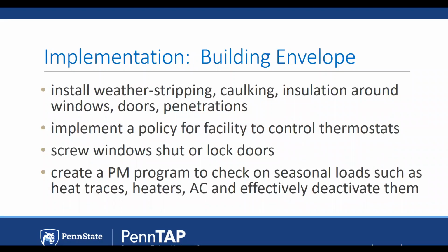For implementation of your building envelope, you would want to install weather stripping, caulking, and insulation around doors, windows, and other penetrations. Also, consider implementing a policy for your facility to control your thermostats. A quick behavior control could be to screw windows shut or to lock doors. Also, create a preventative maintenance program to check on seasonal loads, such as your heat traces, heaters, and ACs, and to make sure that you're effectively deactivating them when they're no longer necessary to use.